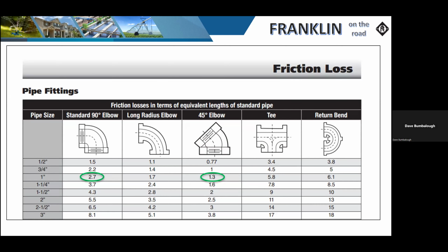One thing I point out here is if you can use 2 45s to accomplish the same 90, you'd be at 2.6. I know you're scratching at the surface, but it's interesting how they calculate these friction losses. If you think about it, it's less of a sharp bend than a 90. So as the water's flowing up, it's basically shooting at a 90-degree turn, whereas on a 45, it's a smoother transition, especially if you have a second one that's still equivalent to 90. It's just not as sharp of a turn. So you're losing basically 0.1, which is not going to add up much, but a little bit here, a little bit there does make a difference.